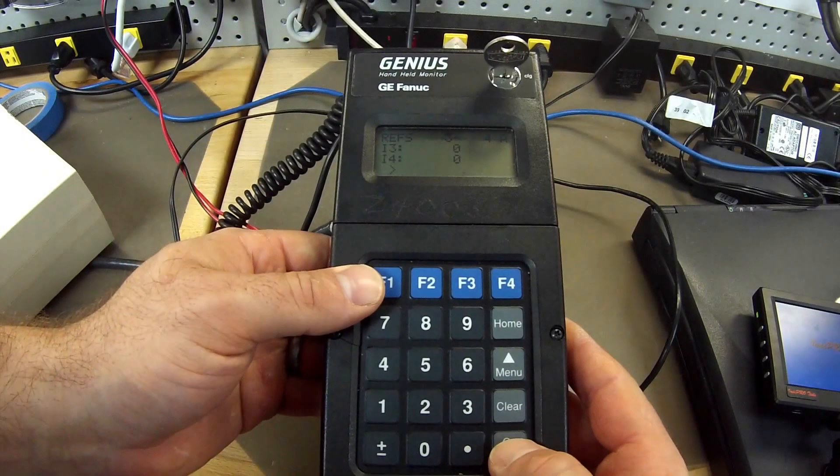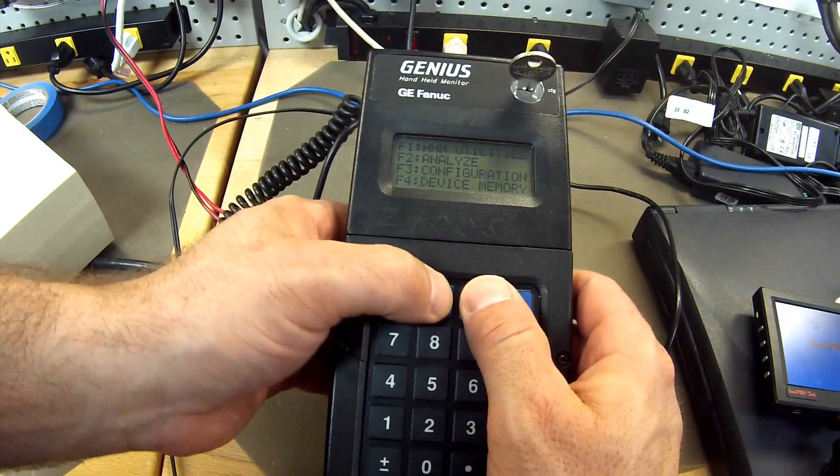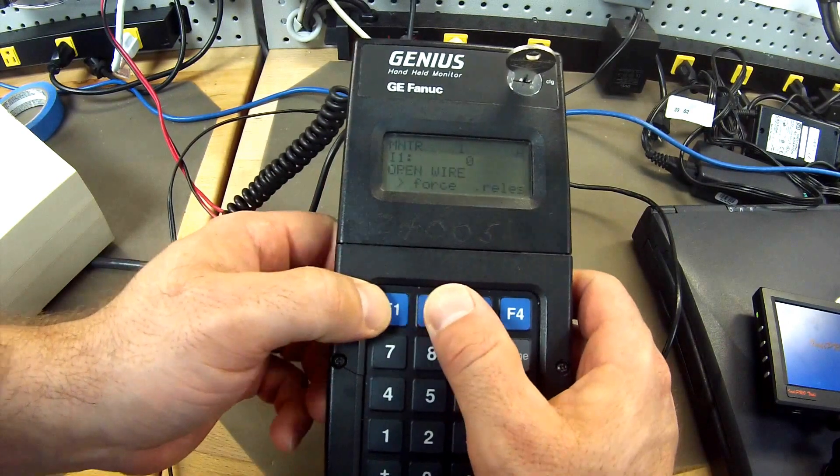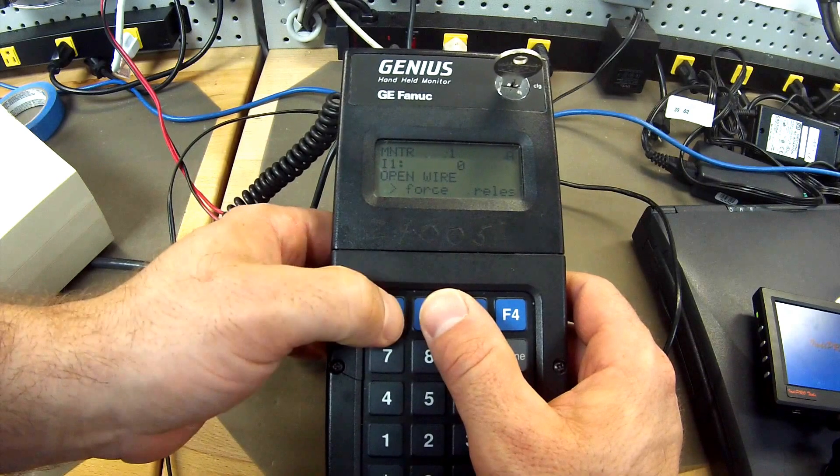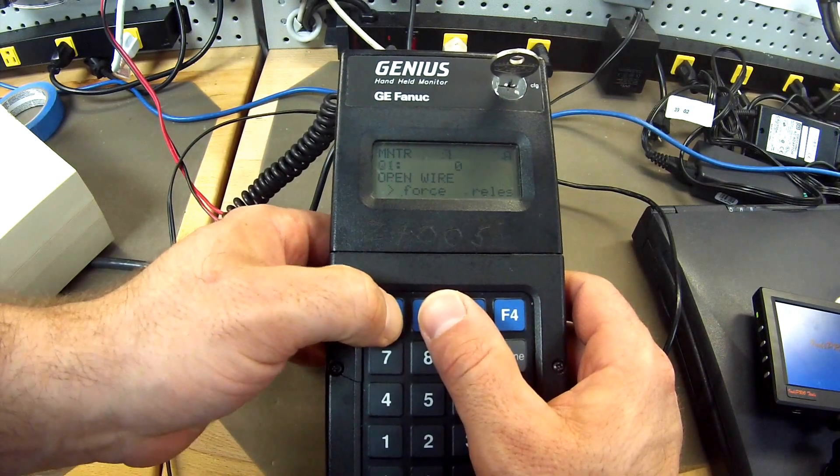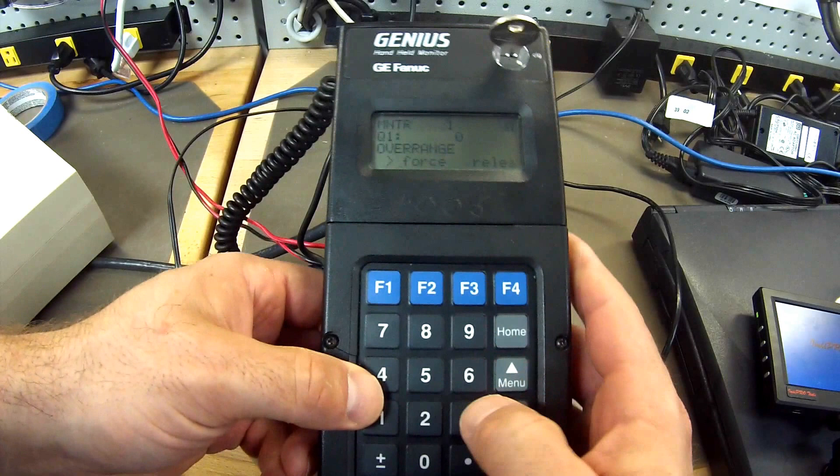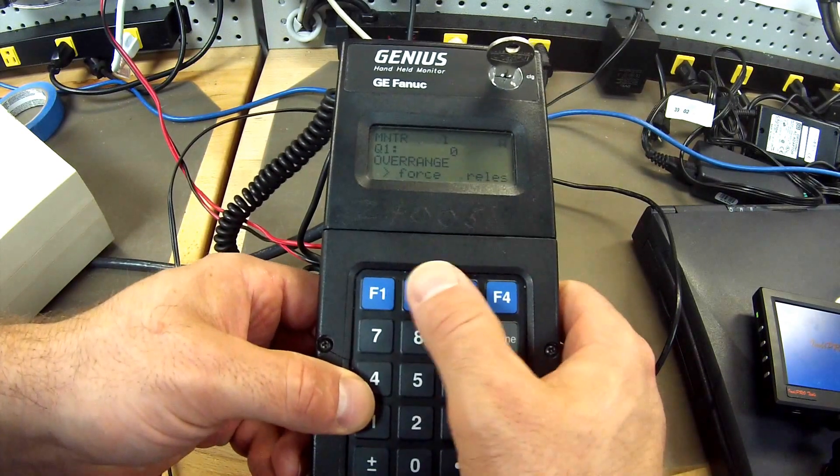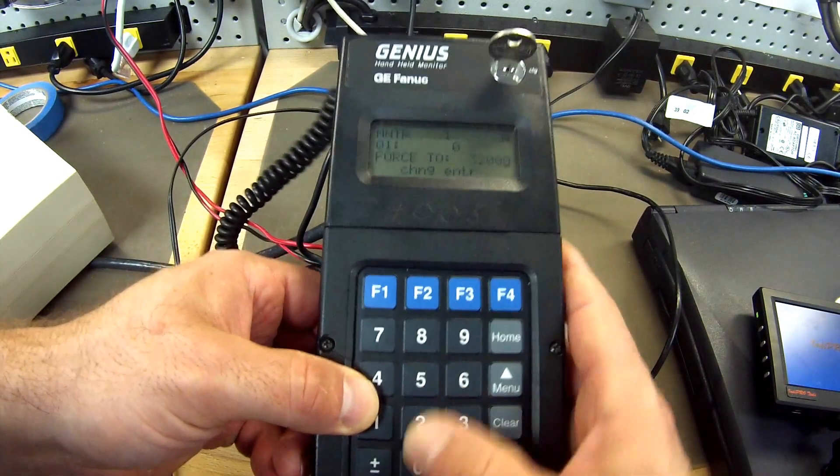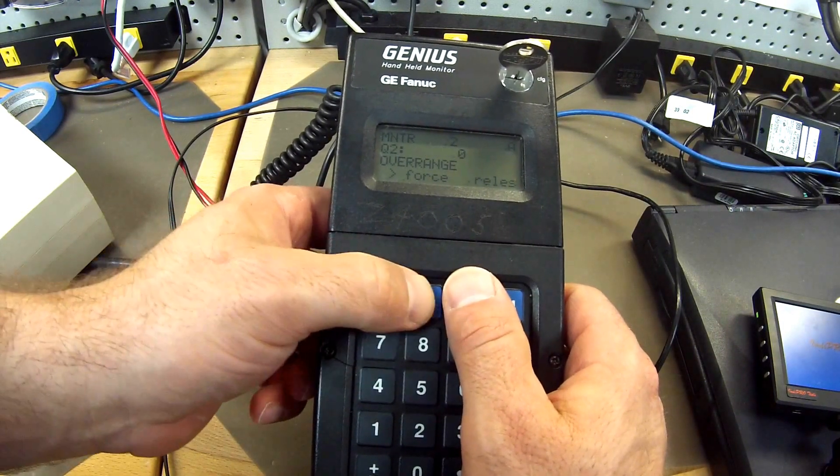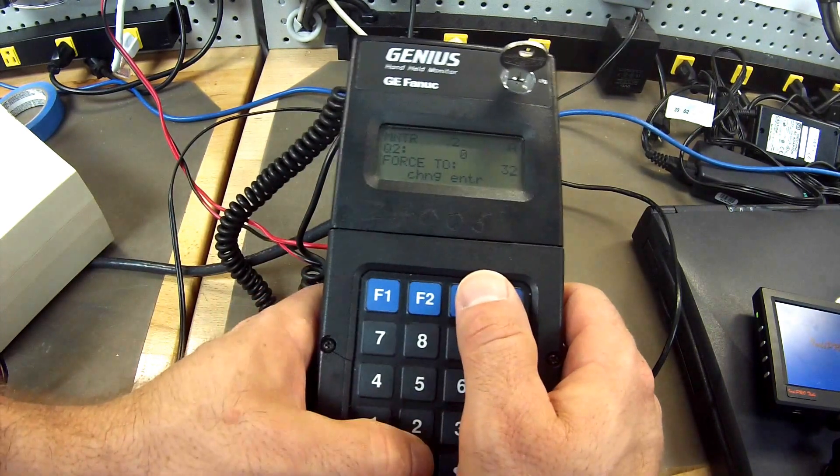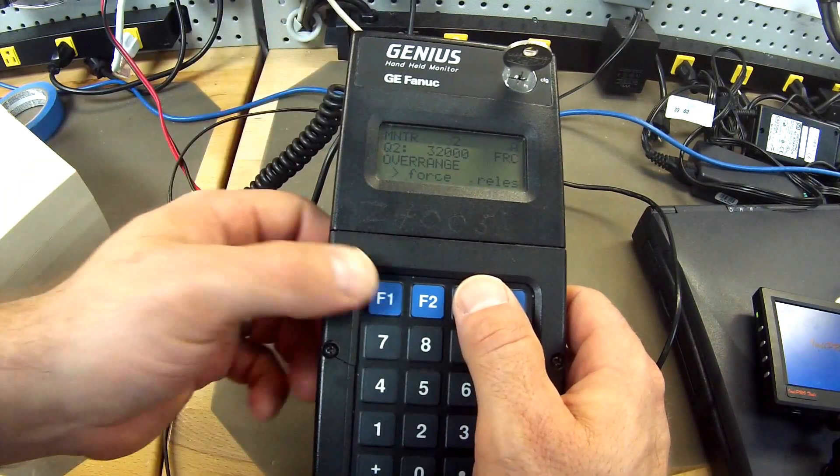Next thing is we want to check our outputs. We will go back to the handheld monitor. I am going to go to home, analyze, monitor, F2. Using the F1 key we go over to 1, 2, 3, 4, output number 1. Same thing I am going to put in that 32,000 value. By hitting force F2, 32,000, enter. Force, 32,000, enter. So now we have values in there.